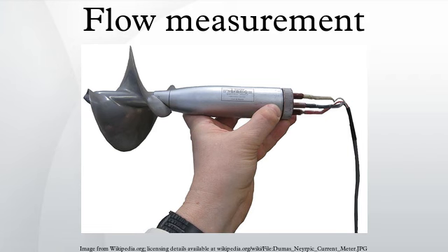Turbine flow meter. The turbine flow meter translates the mechanical action of the turbine rotating in the liquid flow around an axis into a user-readable rate of flow. The turbine tends to have all the flow traveling around it. The turbine wheel is set in the path of a fluid stream. The flowing fluid impinges on the turbine blades, imparting a force to the blade surface and setting the rotor in motion. When a steady rotation speed has been reached, the speed is proportional to fluid velocity.